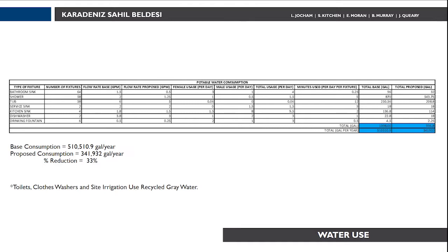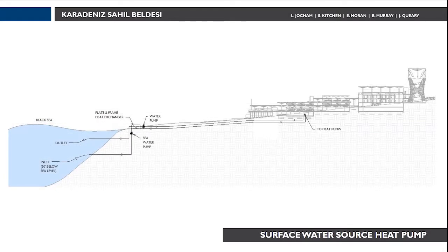The primary heating and cooling system selected by the design team is an open-loop surface water source heat pump. The system uses the Black Sea as its heat source and sink for the water-to-water heat pump system located in the mechanical room. Using the constant Black Sea temperature of 50 degrees Fahrenheit at 50 feet below the water's surface, the system supplies heating hot water at 130 degrees Fahrenheit and chilled water at 40 degrees Fahrenheit.